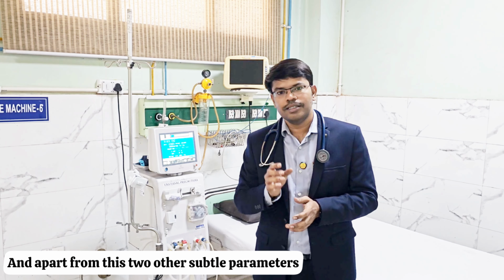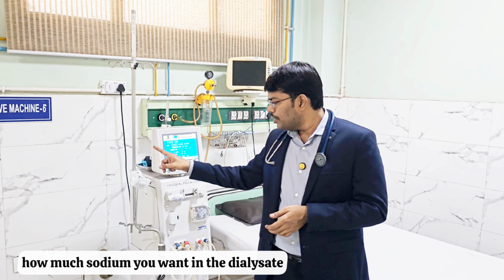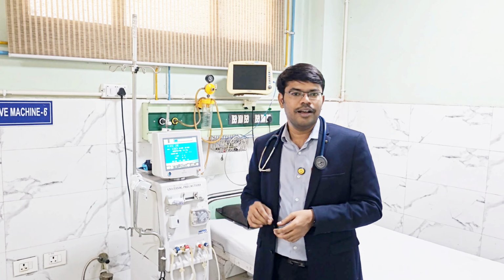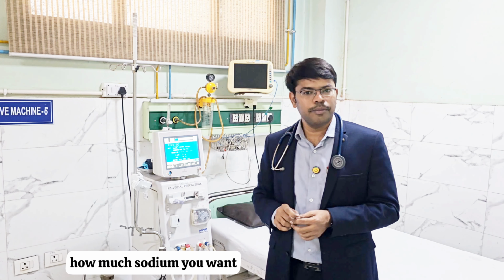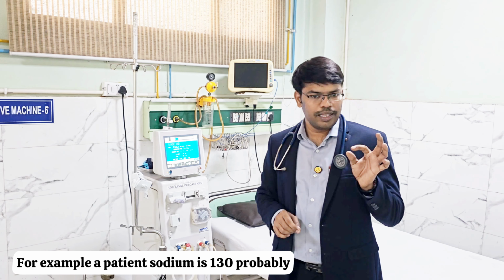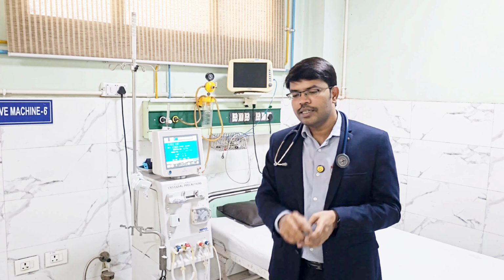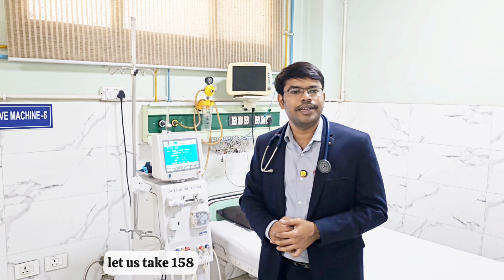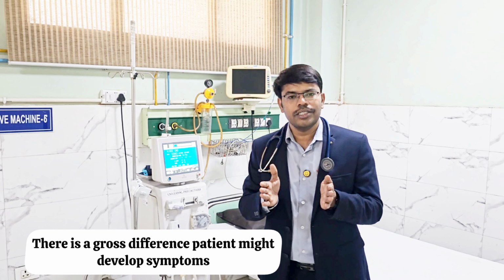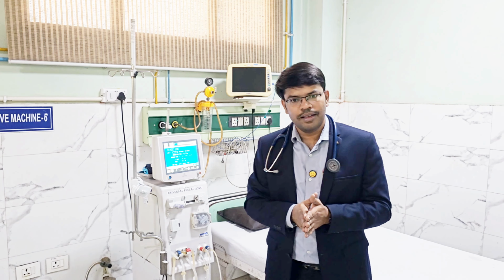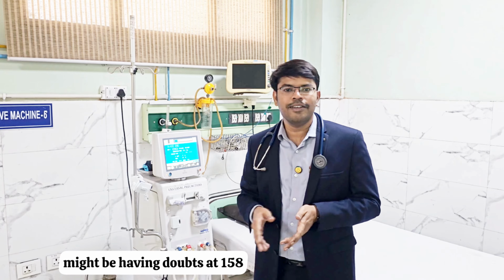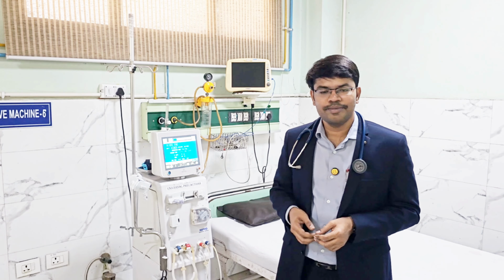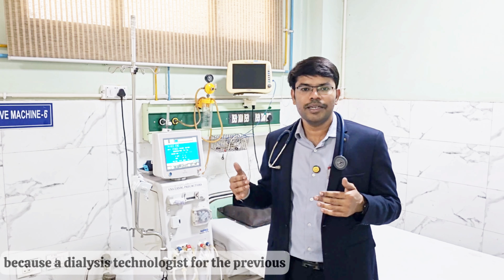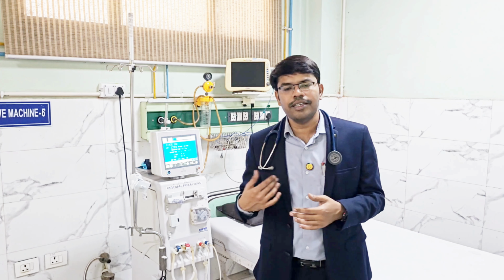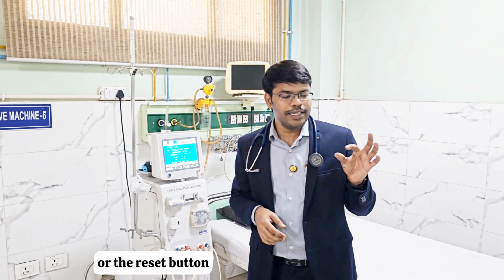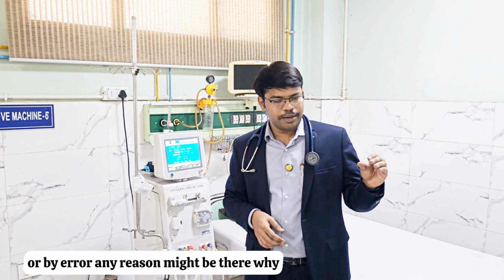And apart from this, two other subtle parameters: how much sodium you want in the dialysate. For example, if a patient's sodium is 130, you need a dialysate sodium approximately similar. Suppose sodium is set at an extremely high level, let us take 158. There is a gross difference, and the patient might develop symptoms. A person watching the video might have doubts: how can 158 be set in the machine? It can be set. Why can this occur? Because a dialysis technologist for the previous patient might have set that parameter and forgotten to reset it, or by error. Any reason might be there.